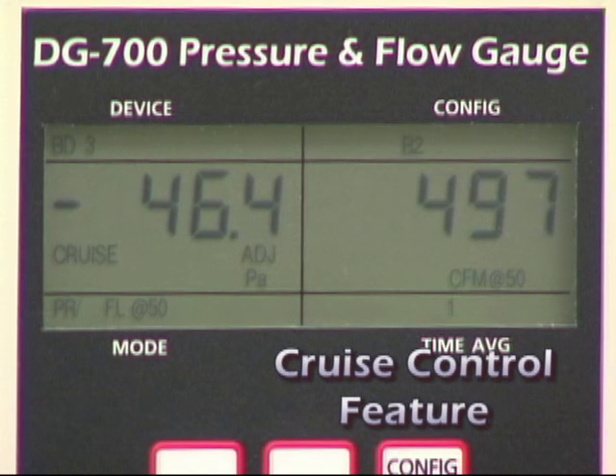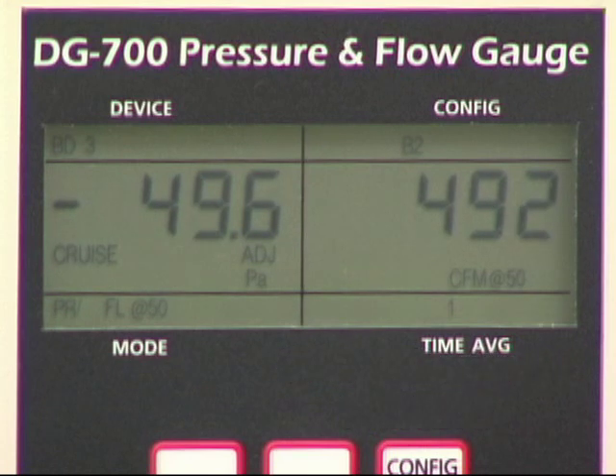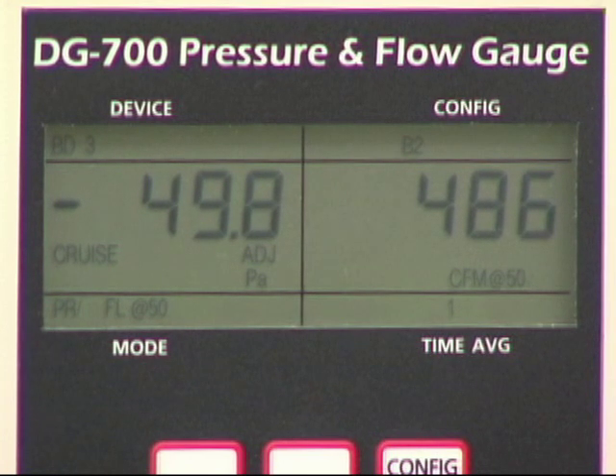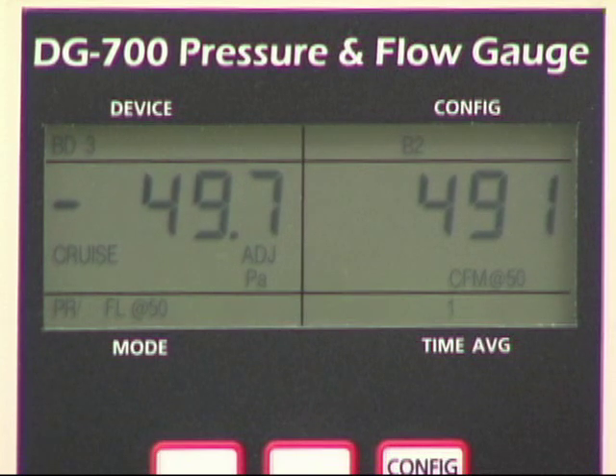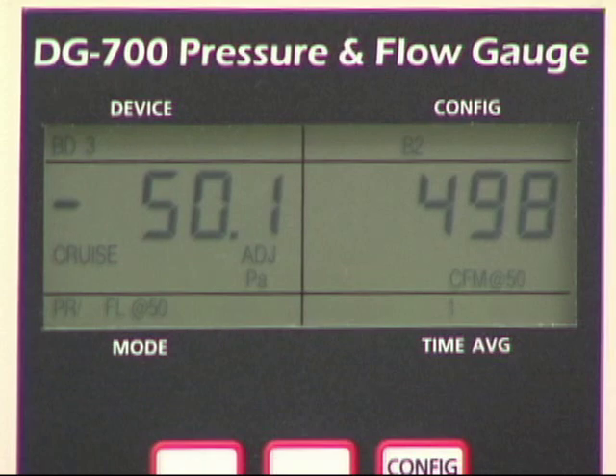Beginning in June 2007, a cruise control feature was added to the DG700, which allows you to automatically control the blower door fan to maintain a constant 75-pascal, 50-pascal, 25-pascal, or 0-pascal building pressure without having the gauge connected to a computer.